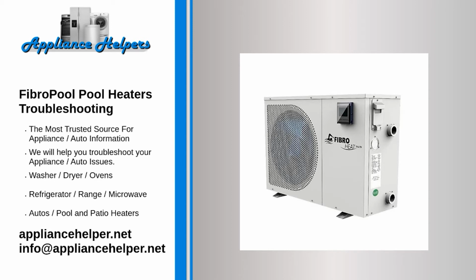Have you inspected the pressure sensor, thermal regulator, and/or the high limit switch? Inspect these parts for corrosion, scaling, and/or any electrolysis issues. If the pressure sensor, thermal regulator, or high limit switch is faulty, corroded, or defective, replace it.